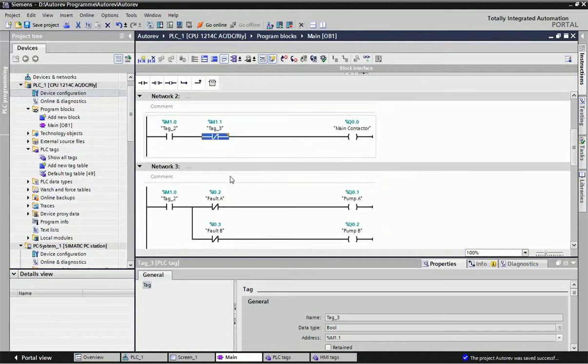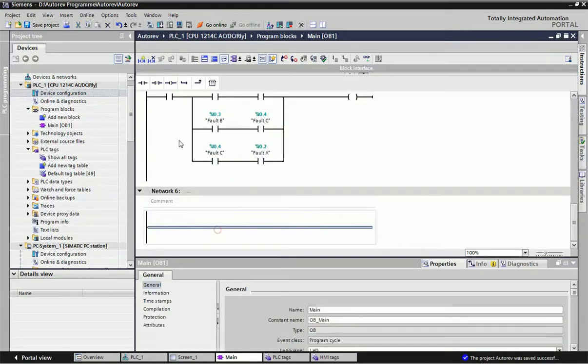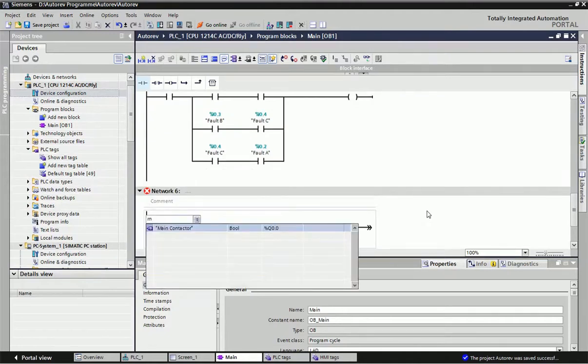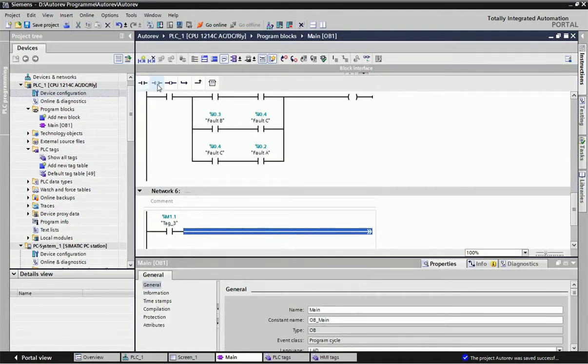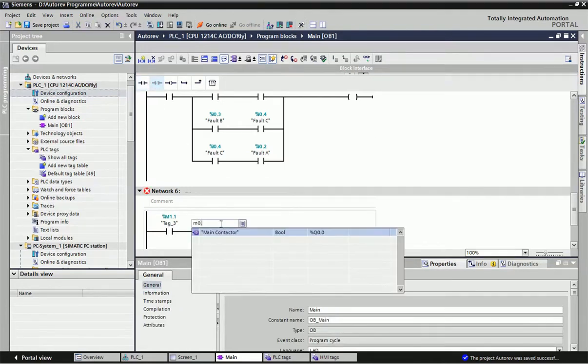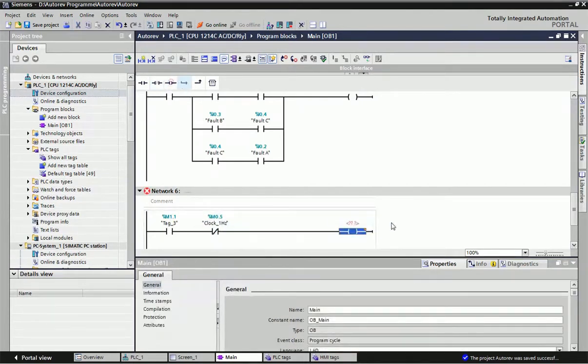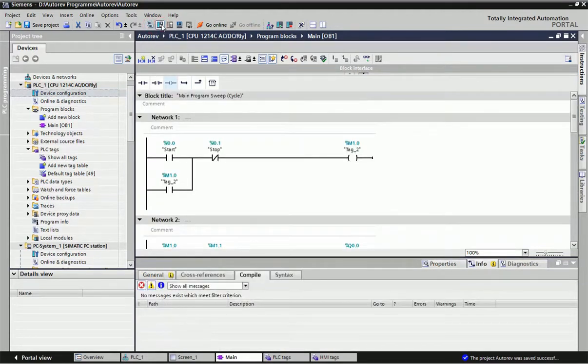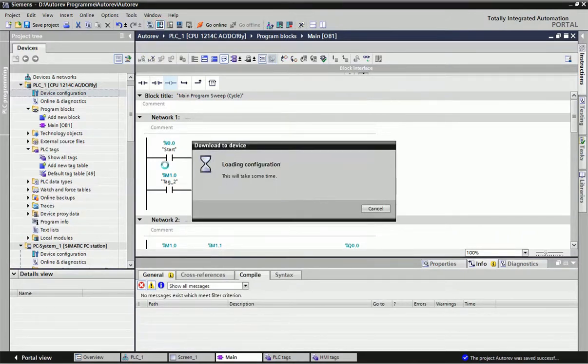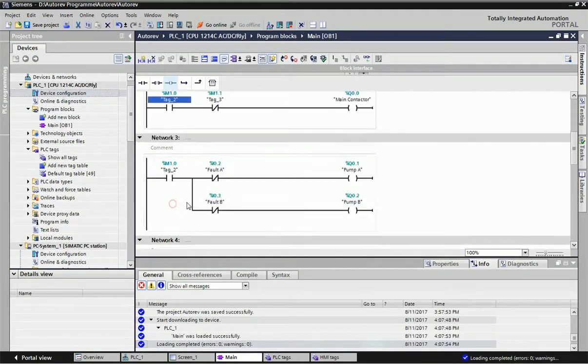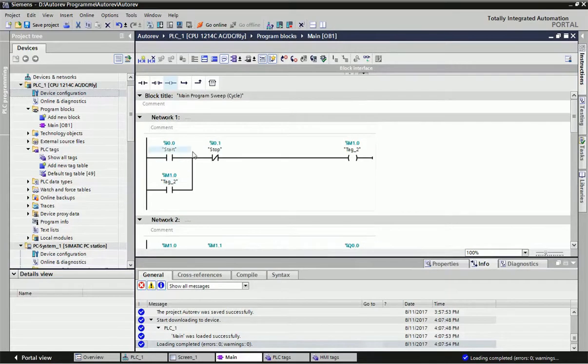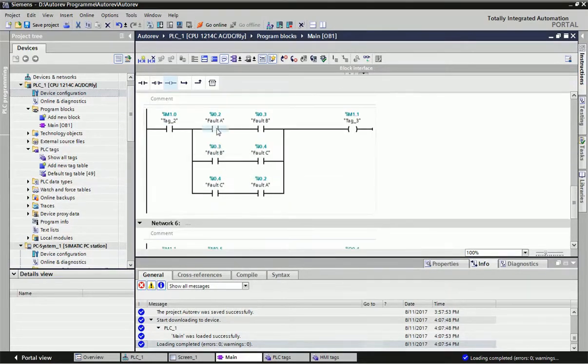For the alarm network, I use M1.1 along with a 1 Hz clock memory bit to drive the alarm bulb output, so it blinks when two pumps have failed. Now our ladder diagram is complete. We will compile and download. As you can see, we have used the same memory bit multiple times across networks — for the start/stop latch, pump control, and fault detection — without rewriting the entire start/stop logic each time.